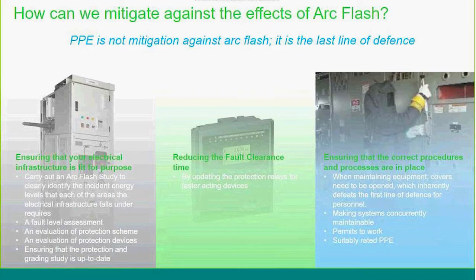And we know it happens. We know items are maintained, pieces of switchgear are maintained whilst the substation's live, particularly withdrawable. So that's an area where we need to think about two different substations having A and B supplies concurrently maintainable. I can switch one off, maintain it whilst keeping the site supplies on. Make sure my permit to work is clear. Maybe include the arc flash incident energy level ratings in the permit to work, so whoever's working in that environment knows what level of PPE they need to equip themselves to go into that area.